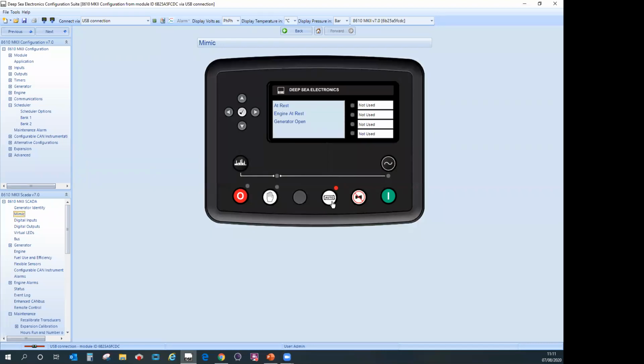If you're in auto mode, the generator won't start unless it either receives a remote command, via a digital input telling it to start, or a mains failure occurs. This is an 8610, so there's no mains failure protection on it. So the only reason this generator would start would be if someone flicks the switch remotely, or the scheduler kicks in. We configured the scheduler earlier. If that kicks in, say it's Monday morning 8 o'clock, the generator will automatically start. So that's auto mode.